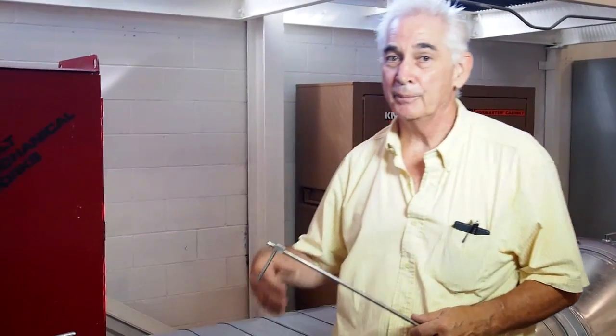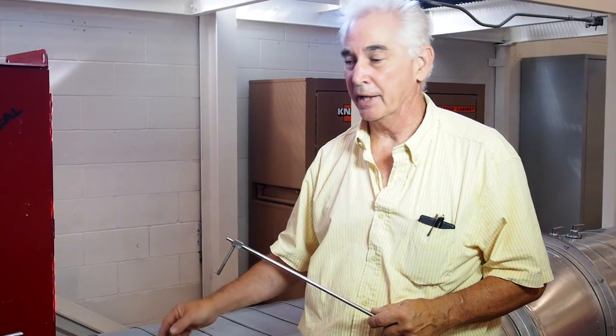You'll have a lot of readings, but again, you take the readings, velocity pressure, convert them to velocity, take the average of all your velocities times the area of the duct.